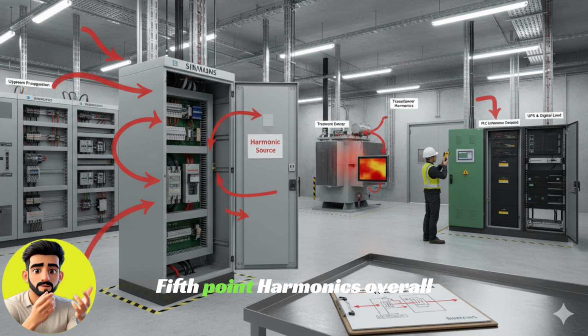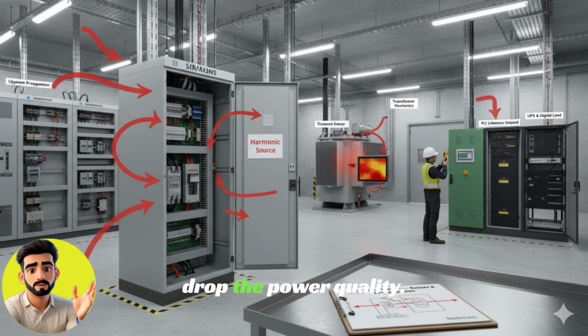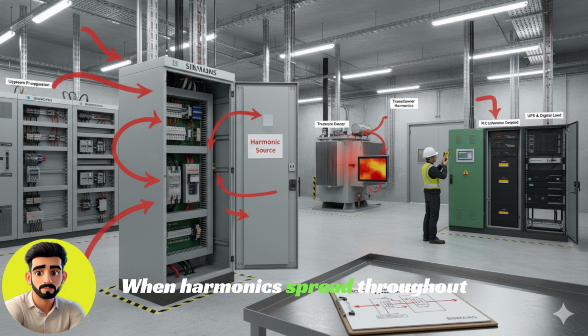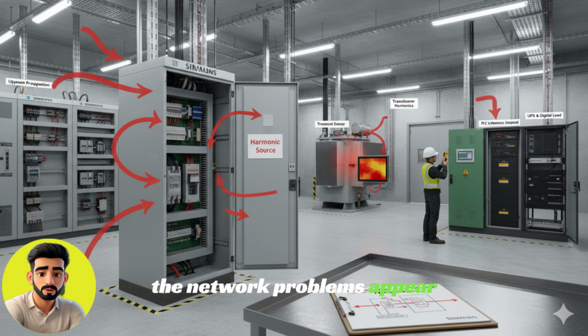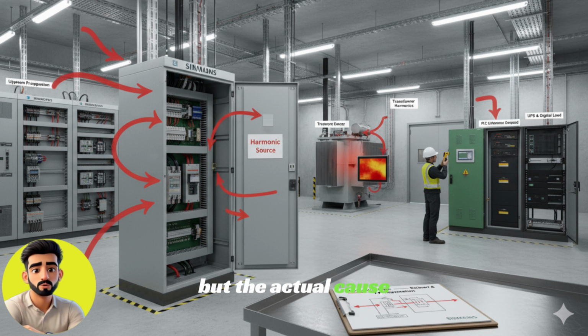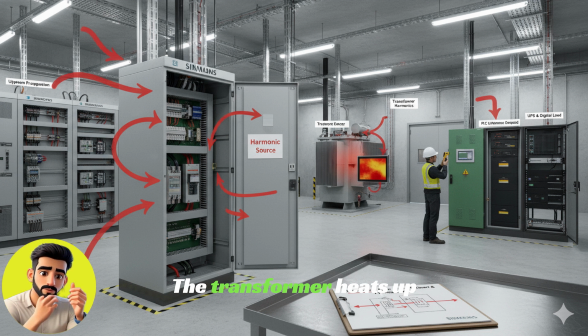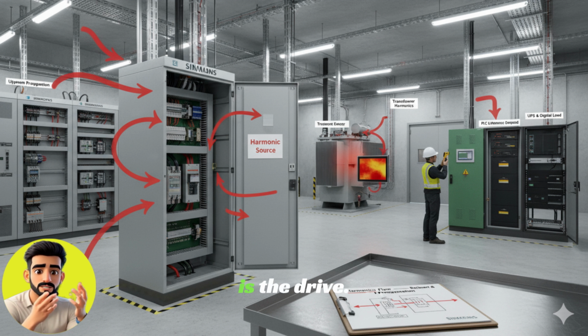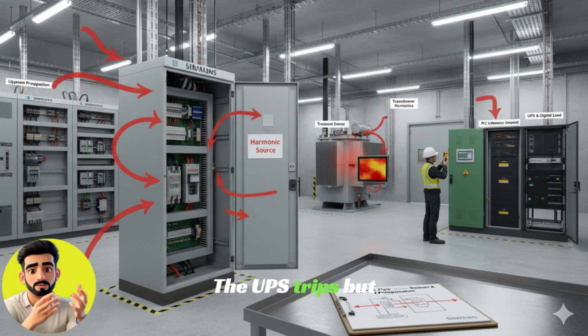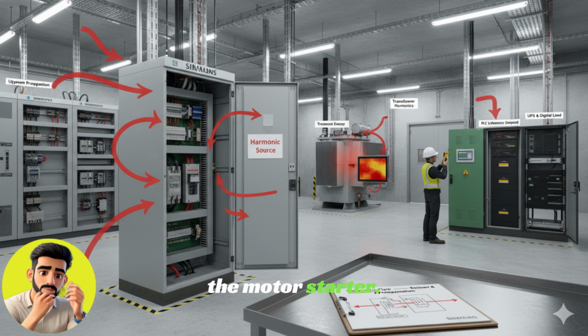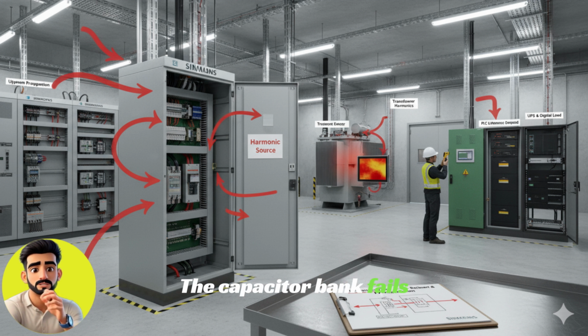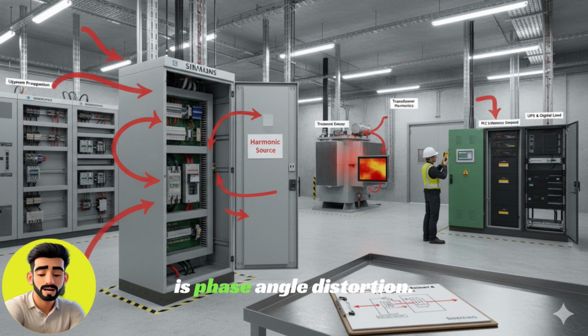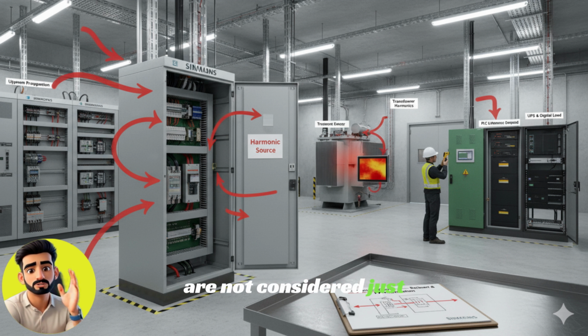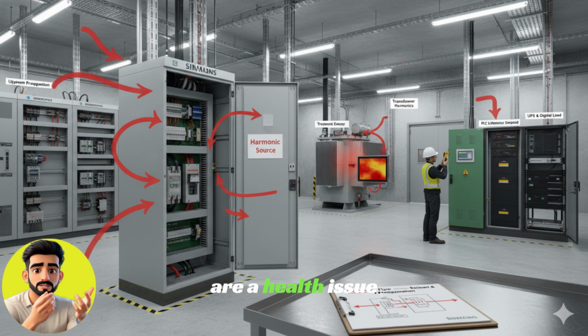Fifth point, harmonics drop the overall power quality. When harmonics spread throughout the network, problems appear at a certain point, but the actual cause is elsewhere. The transformer heats up, but the root cause is the drive. The UPS trips, but the root cause is the motor starter. The capacitor bank fails, but the root cause is phase angle distortion. That is why harmonics are not considered just a local problem. They are a health issue for the entire plant.